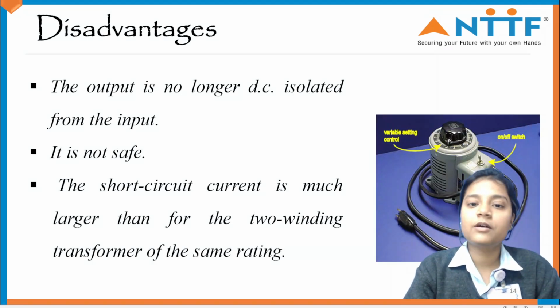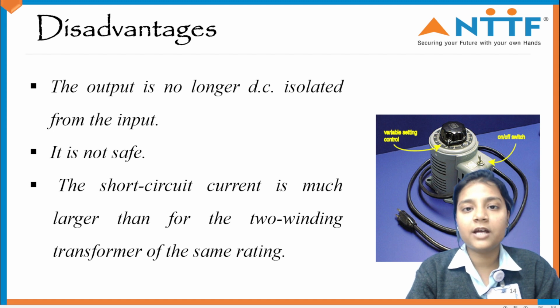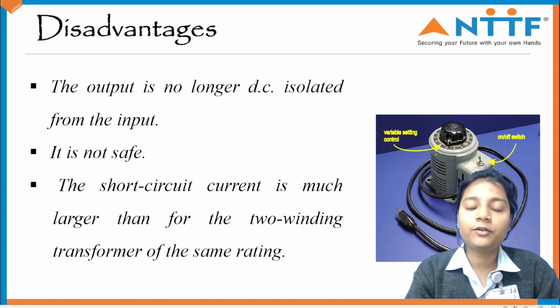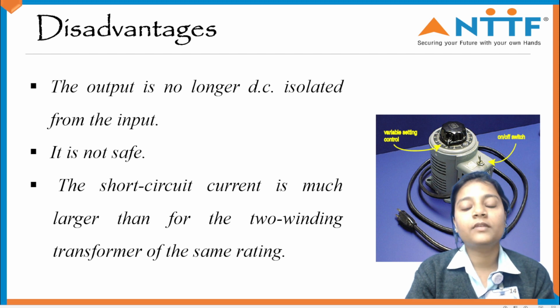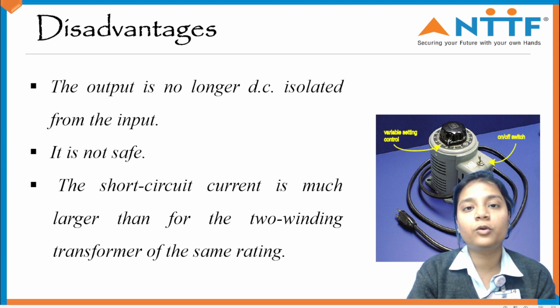Talking about the limitations, the output is no longer isolated from the input, as we use a single winding, so there is no isolation between the windings but a magnetically coupled device. It is not safe for operation because of the lack of isolation. The short circuit current is much larger in this case as compared to a two winding transformer. Another point that I would like to discuss is that the auto transformer could not be rated above 420 volts. So it is generally used for low voltage applications in industries and laboratories for education.